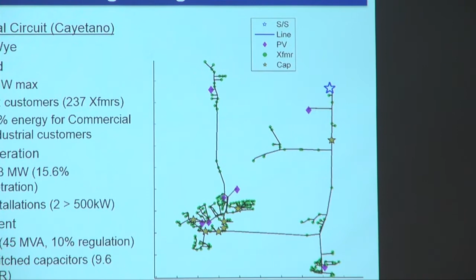So what are some of the challenges associated with this? The traditional way of managing the flow of power and voltage distribution on the circuit must be changed, and sometimes equipment must be added to keep voltage within limits. We looked at that circuit in its original configuration, and then added various amounts of PV power, and you can see the voltage distributions change quite substantially, sometimes with very high voltage levels near the end of the circuit, because of substantial backflow of power toward the substation.